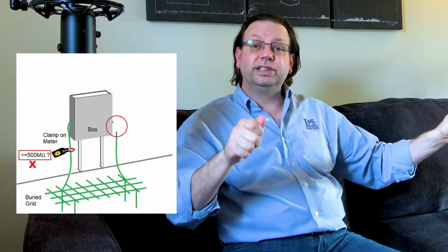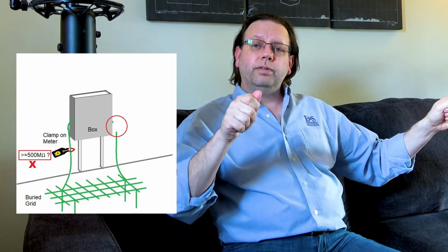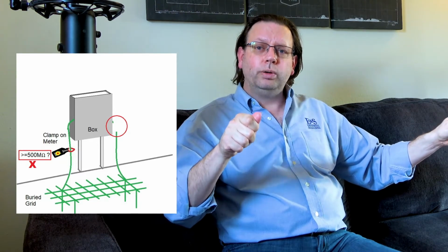Okay. When we did our standard traditional 2-point meter, where we came from the ground bar, we went out to that switch. If we checked that ground wire, we said it was kind of close, it was on the case, but we didn't know there was a bunch of corrosion between the case and the ground wire, so it was actually open and wasn't connected because of the corrosion. Our 2-point continuity meter would have shown that as still being a nice low fault current impedance path. It would have measured that.